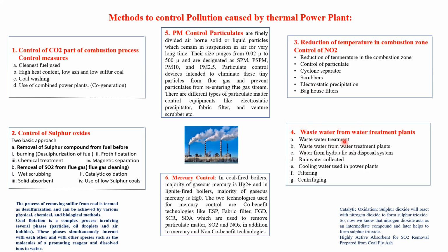We call it an effluent sump, and in this case some chemicals are added to the water so it can be treated, and that wastewater can be used in some parts of the plant, such as firefighting, raw water wherever required, fly ash removal, bottom ash removal, etc. For that, the water can be reused. So water from the hydraulic ash disposal system, that is the ash disposal system, can also be reused.